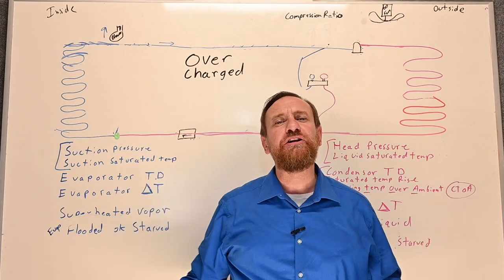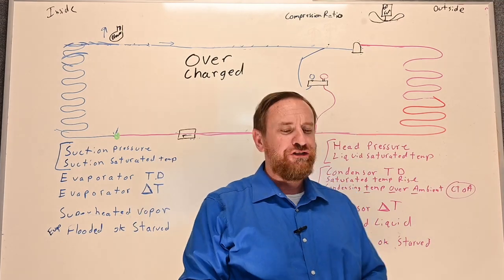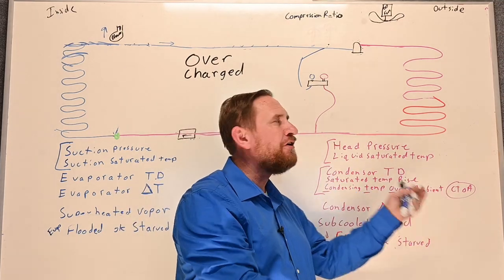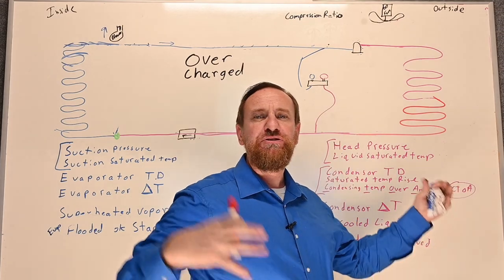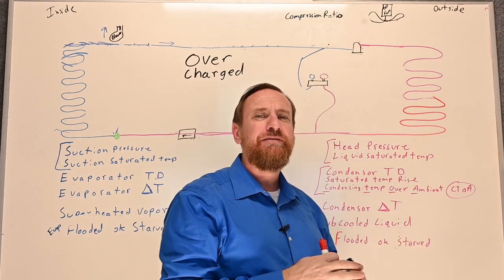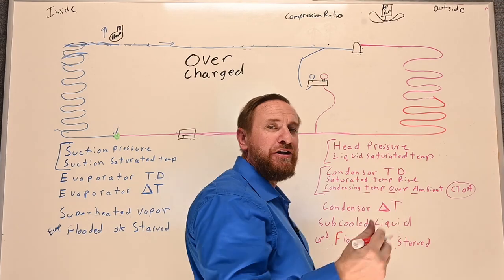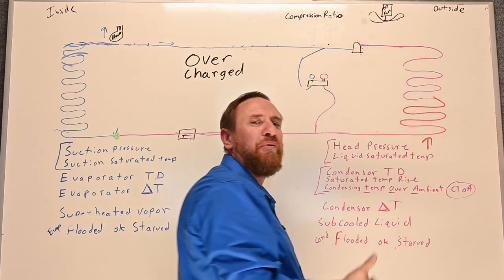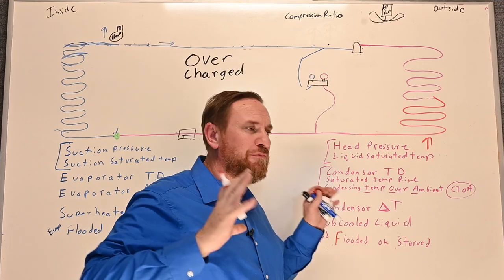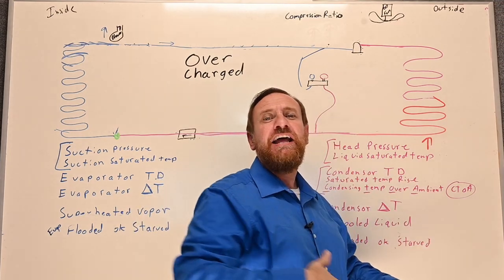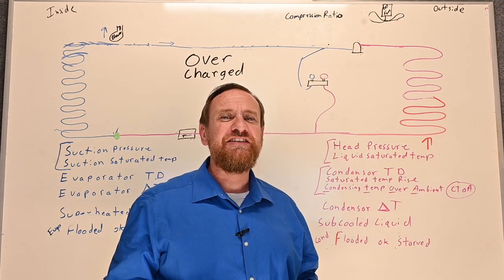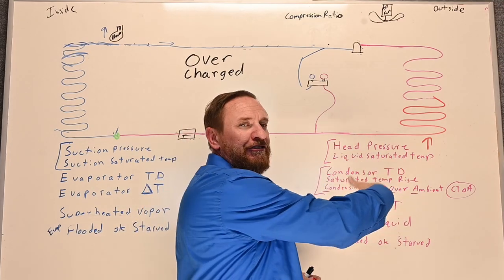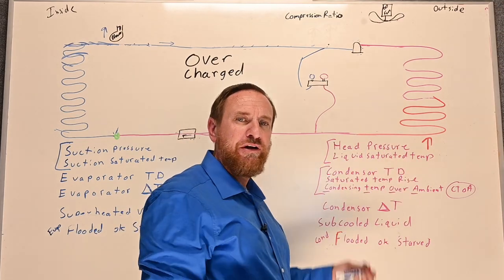An overcharged system means there are extra molecules — more molecules of refrigerant. As we add more and more molecules of refrigerant, what do you think the head pressure is going to do? It's trying to push more molecules into that same area. The head pressure is going to go up, because we have more molecules being squished together. If I put more molecules of air in a tire, the tire pressure goes up. So more molecules of refrigerant — too much refrigerant — is going to cause the pressure to go up.